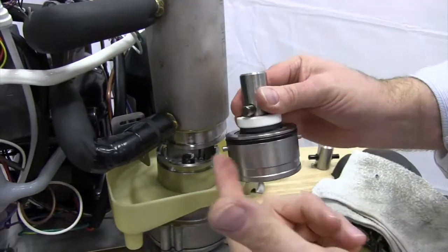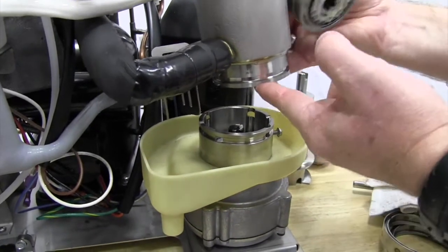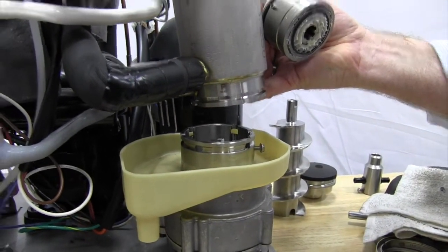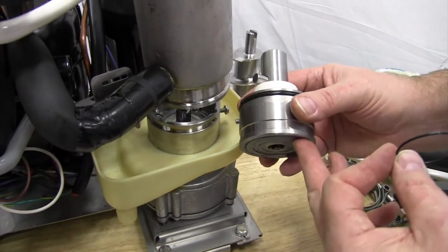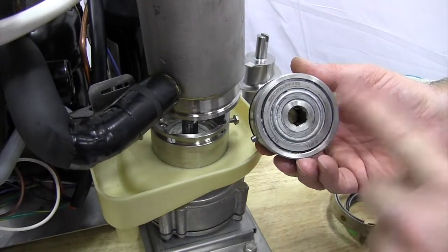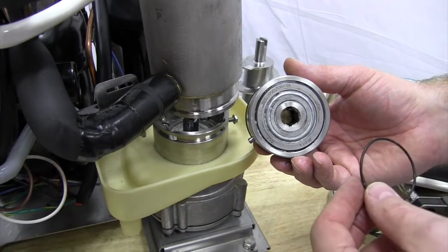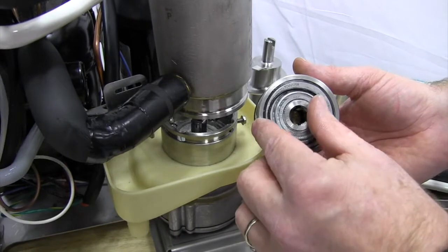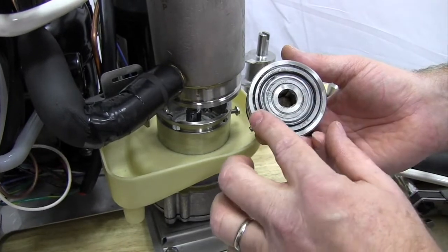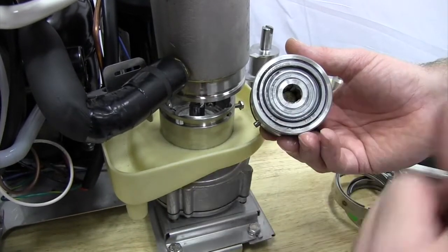Notice there's a couple of roll pins on either side. These roll pins fit into corresponding notches down in the cup and also notches that are up in the underside, the lower section of the evaporator. I've got the lower bearing out. I've wiped off some of the grease that's on here. The grease that we use is a Mobil FM222 grease - you can find that in our service manual. There's also an O-ring that's going to be down inside the cup. What that O-ring does is it sits on the bearing, and it keeps condensation from getting into the bearings.